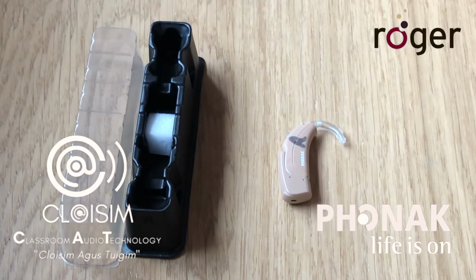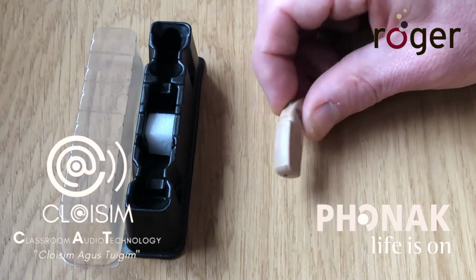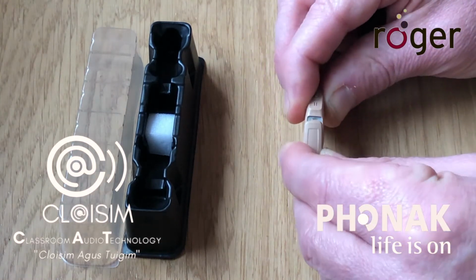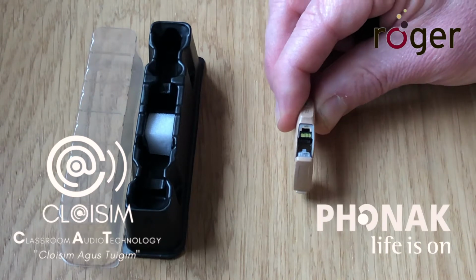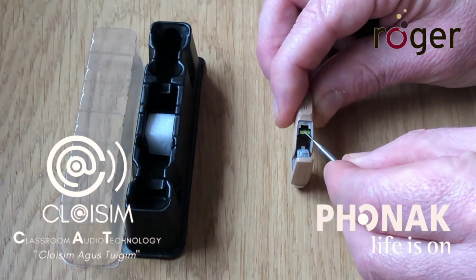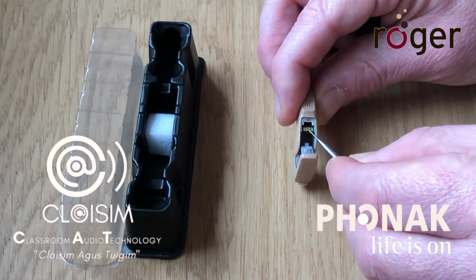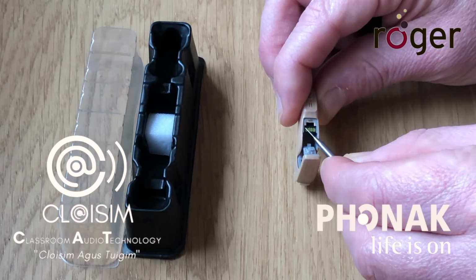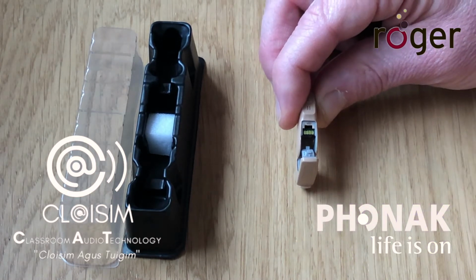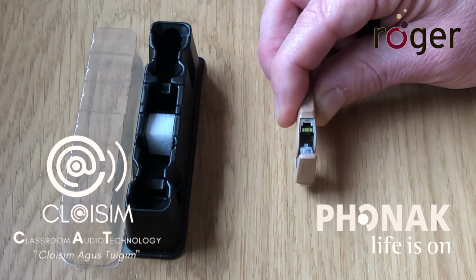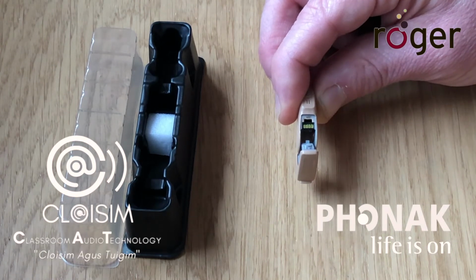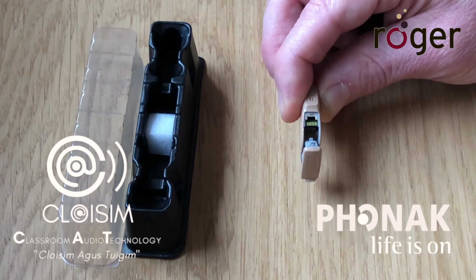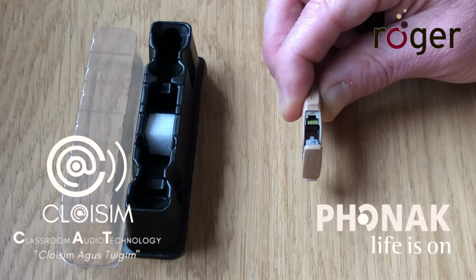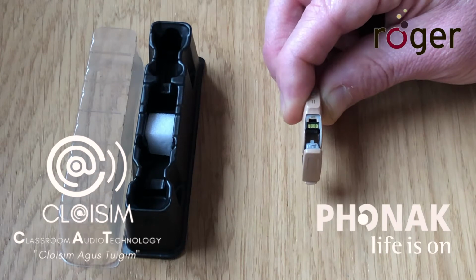You've now put your receiver on. The next thing I want to show you is some connections, contacts. These are four brass rectangular contacts on the hearing aid itself. They exist on all the hearing aids, no matter what model they are. They are used to take the power from the battery up to the hearing aid and into the receiver, and also to take the signal from the receiver up to the hearing aid.